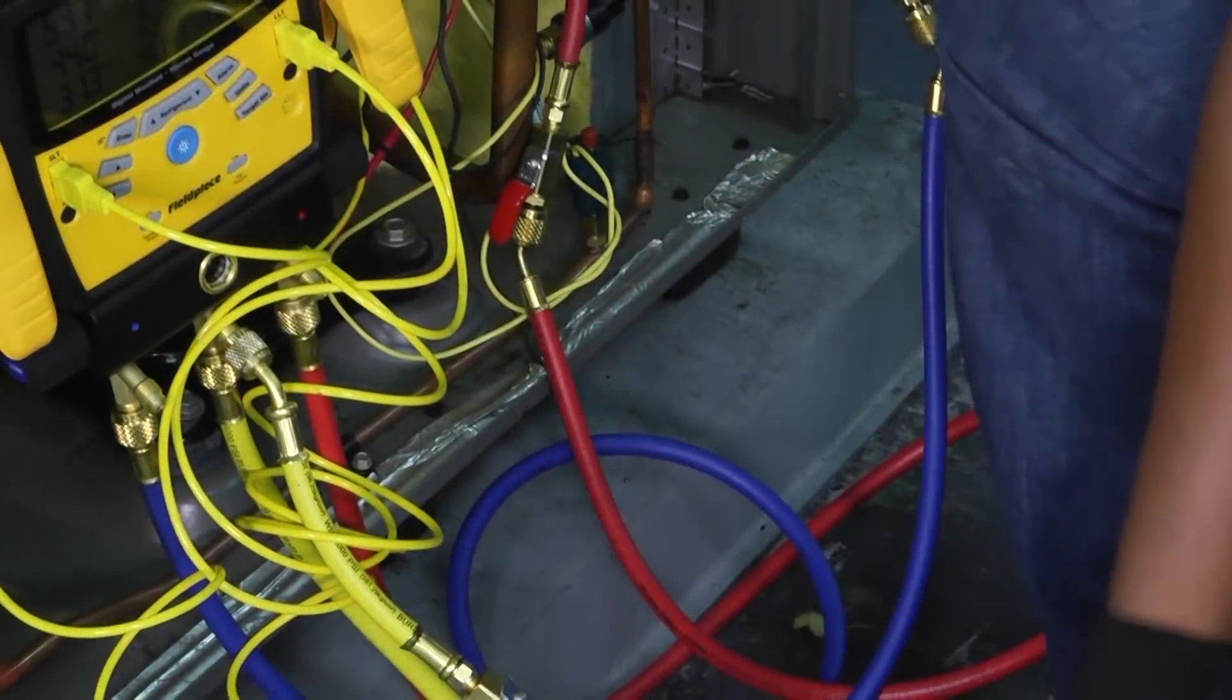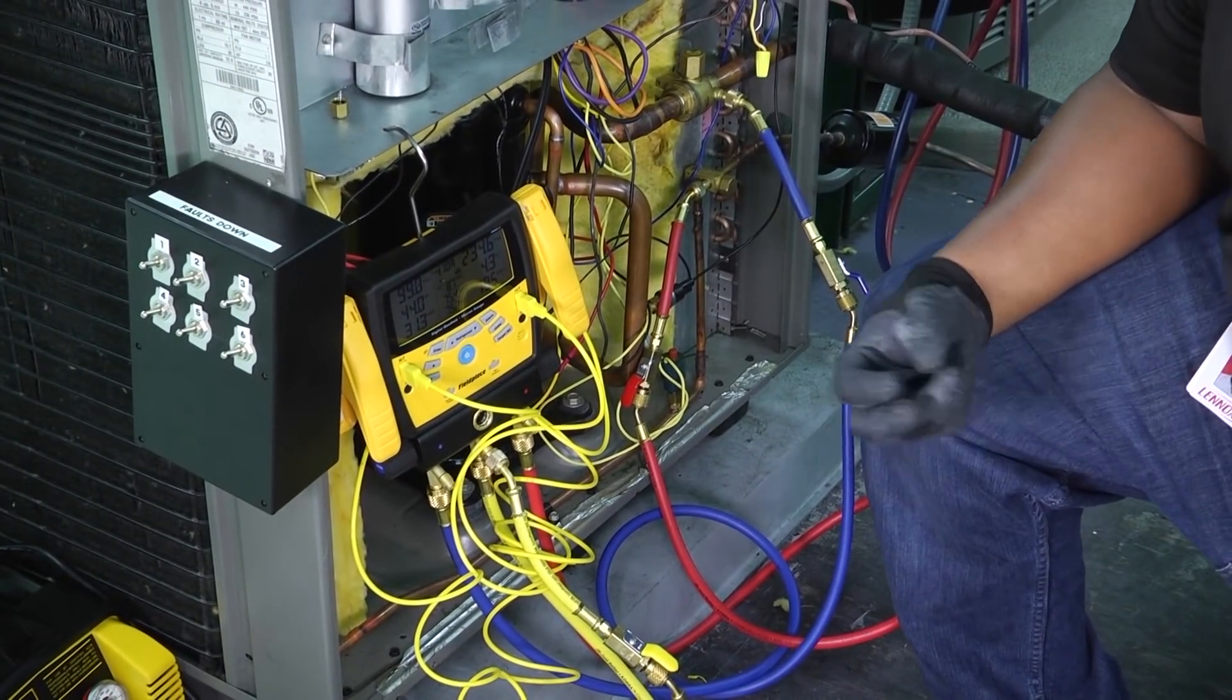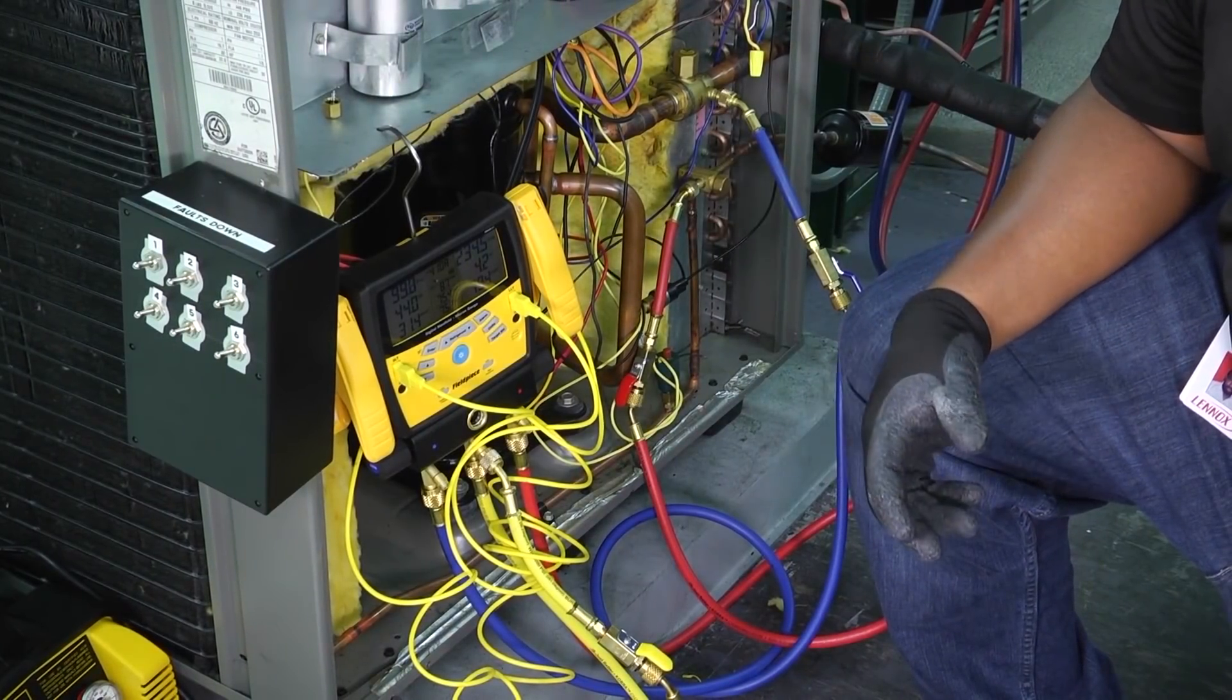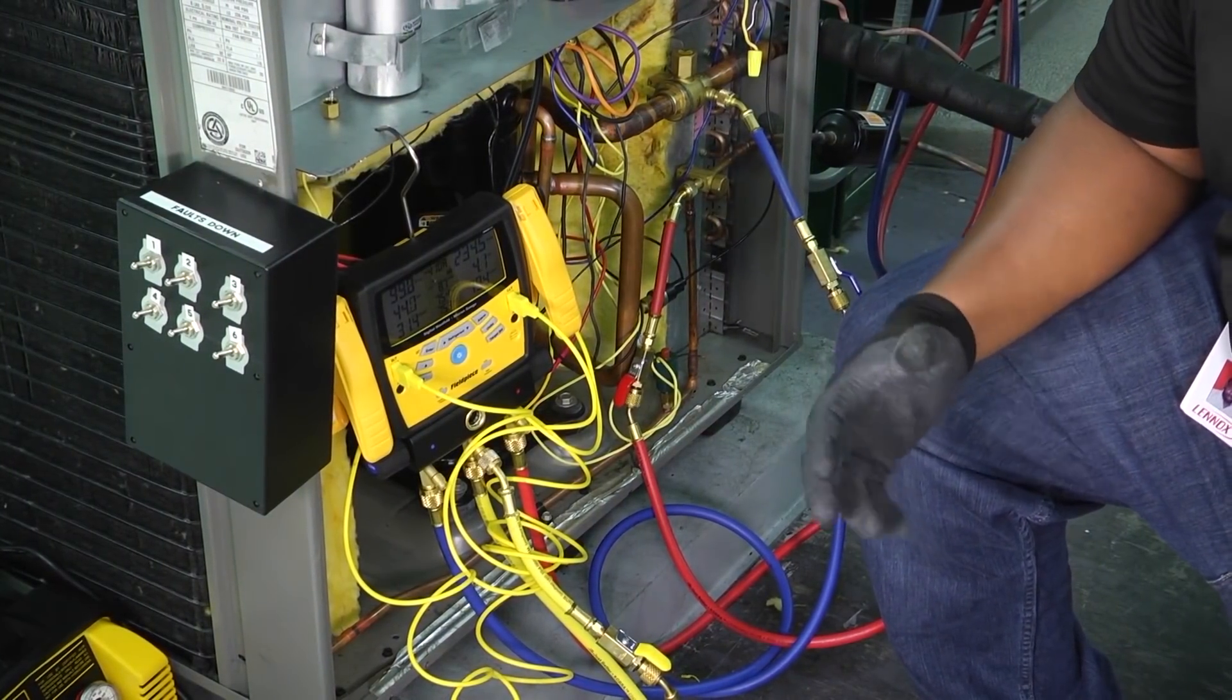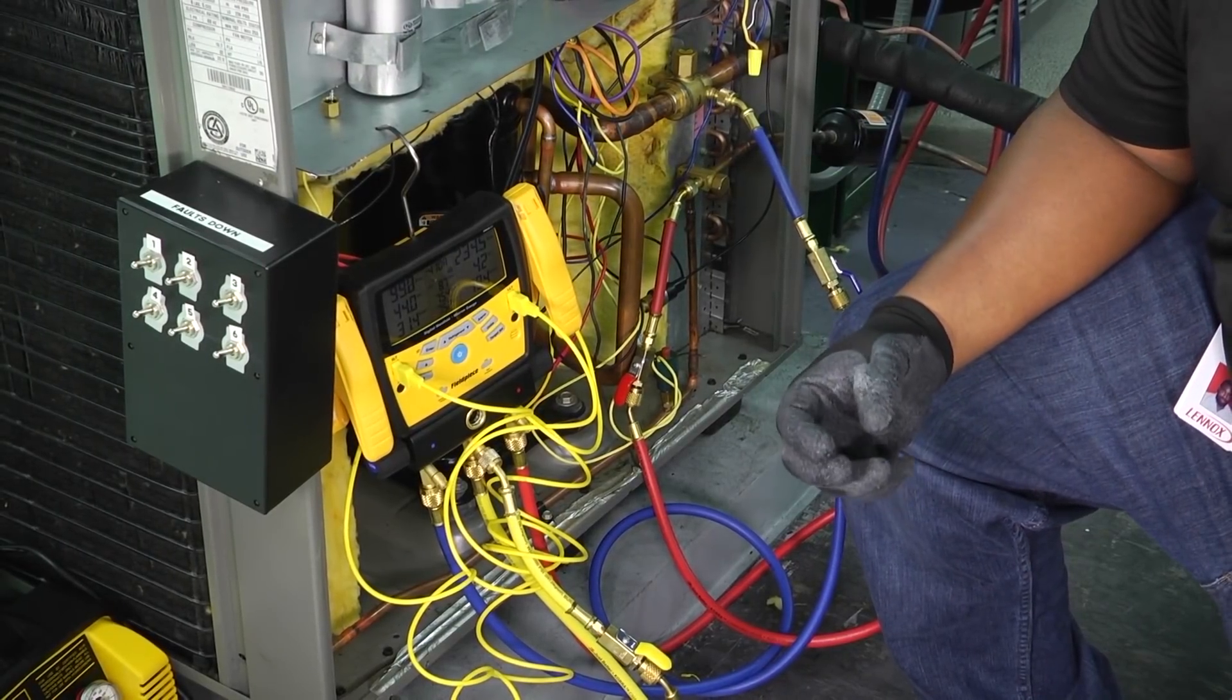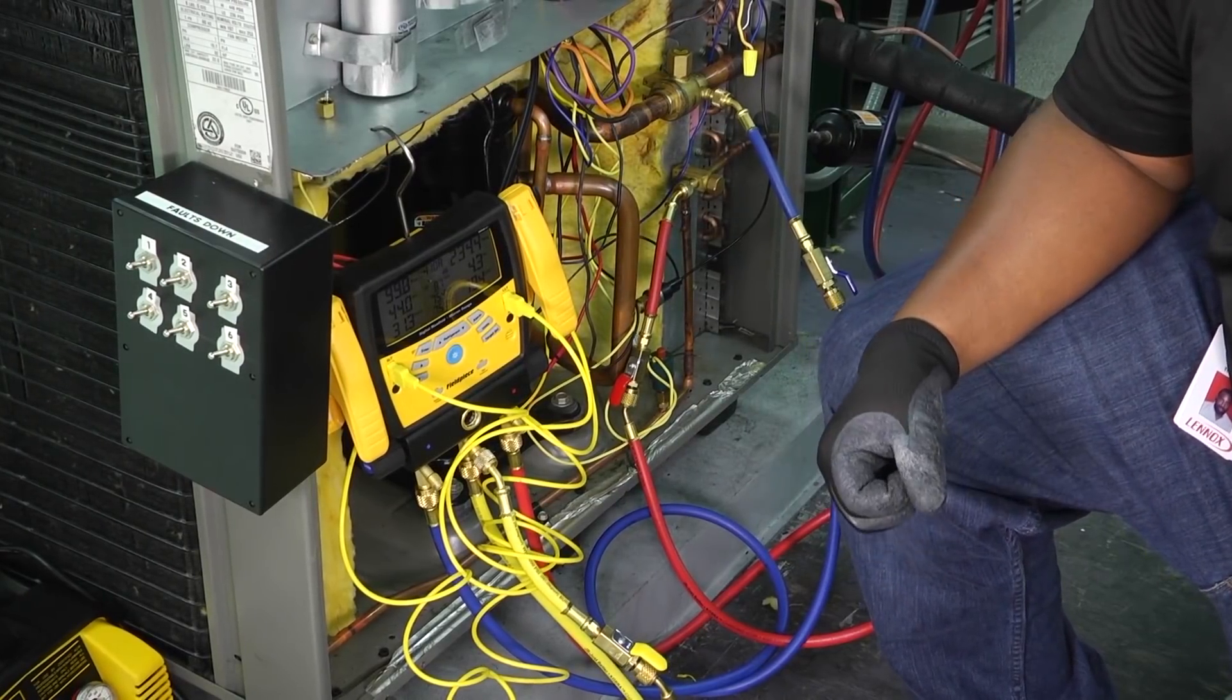Should you have a TXV system, we know that a TXV system is going to maintain a constant superheat of 10 to 15 degrees. So, that number, if that TXV is working properly, should stay within that range. Now, the amount of humidity or moisture content that we have in the air could affect that a little bit, but for the most part, 10 to 15 is going to be the number that we're looking for.